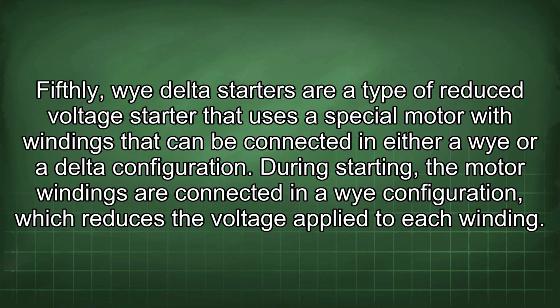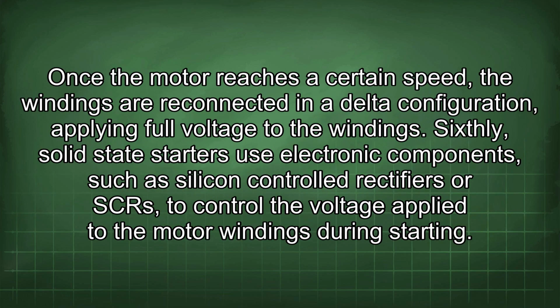Fifthly, Y-delta starters are a type of reduced voltage starter that uses a special motor with windings that can be connected in either a Y or a delta configuration. During starting, the motor windings are connected in a Y configuration, which reduces the voltage applied to each winding. Once the motor reaches a certain speed, the windings are reconnected in a delta configuration, applying full voltage to the windings.